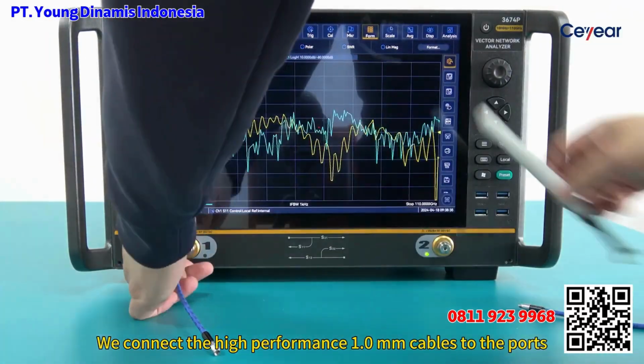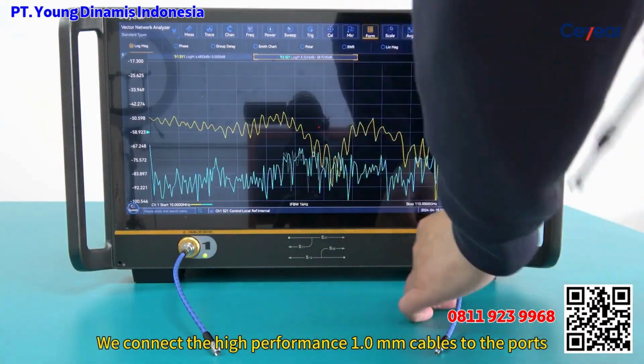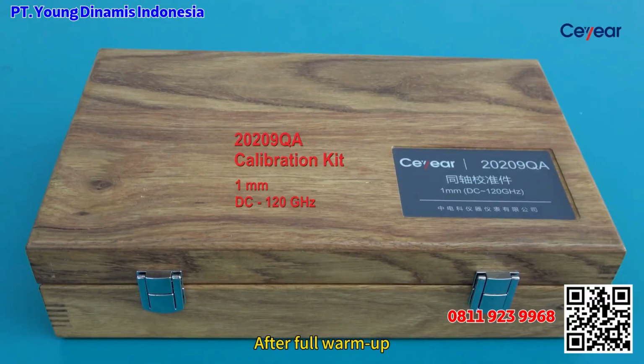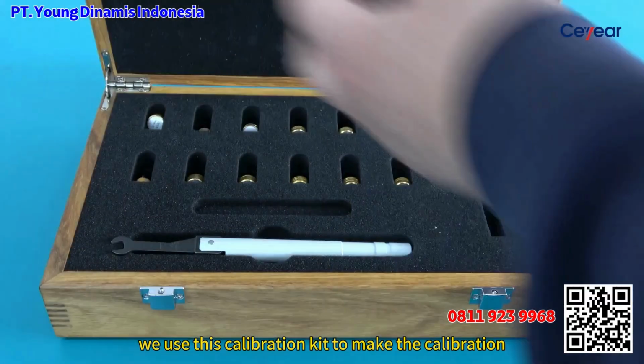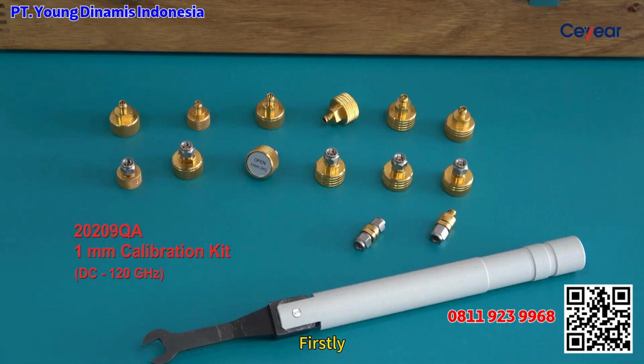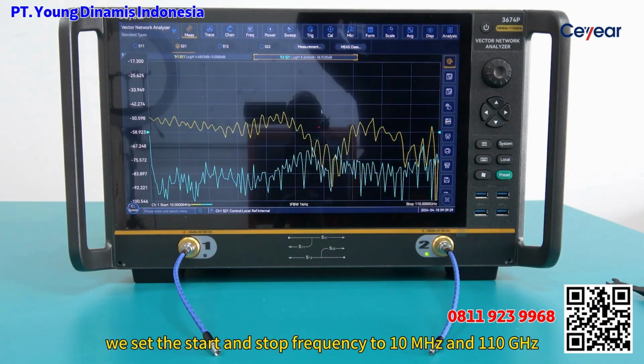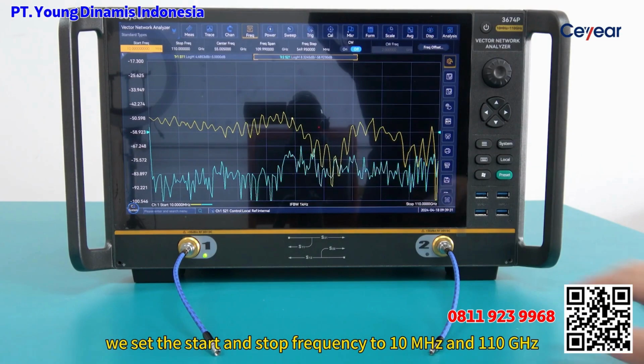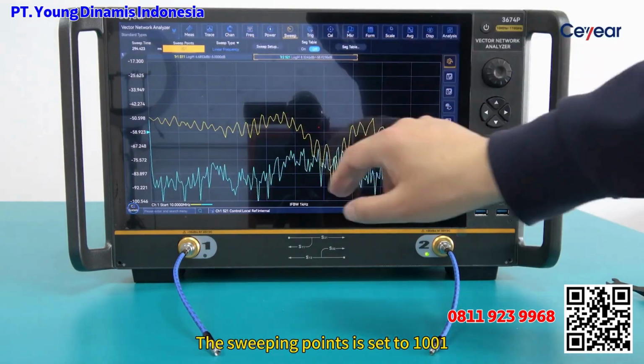We connect the high-performance 1.0mm cables to the ports. After full warm-up, we use this calibration kit to make the calibration. Firstly, we set the start and stop frequency to 10 MHz and 110 GHz. The sweeping point is set to 1001.